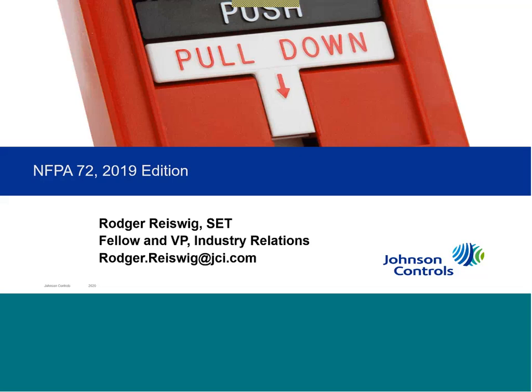When I send a device to UL, they verify that the device functions per the standard. Then they ask me for my installation and service instructions. And they verify that how you say to install it, they install it that way and make sure that it works properly like that. They're going to inspect it the way you say. They're going to test it and service it the way you said. So they verify all that documentation.